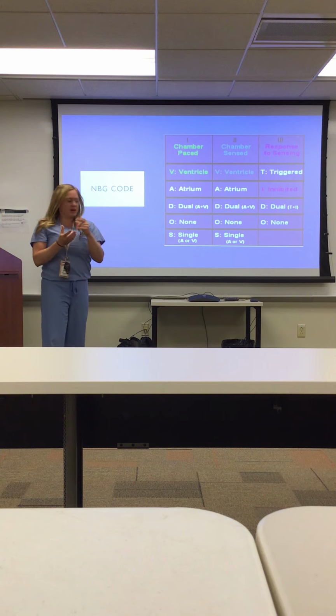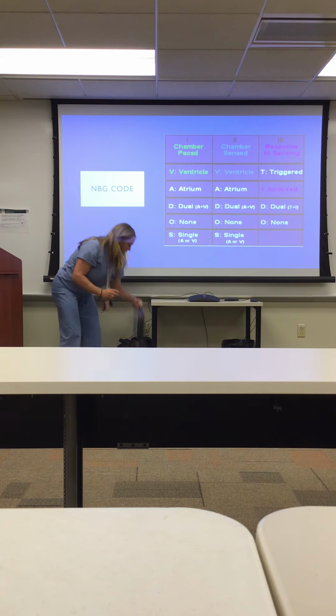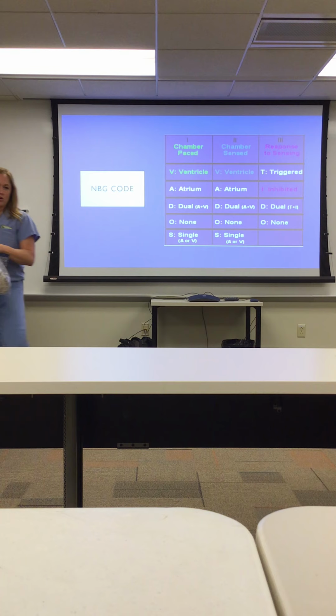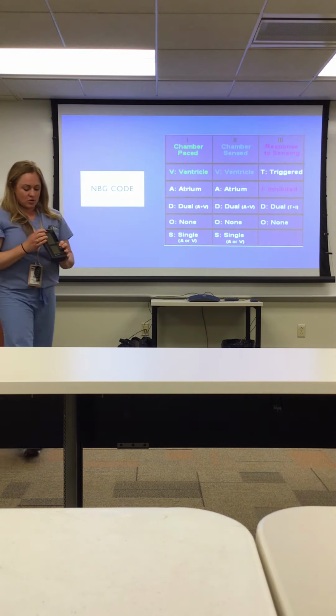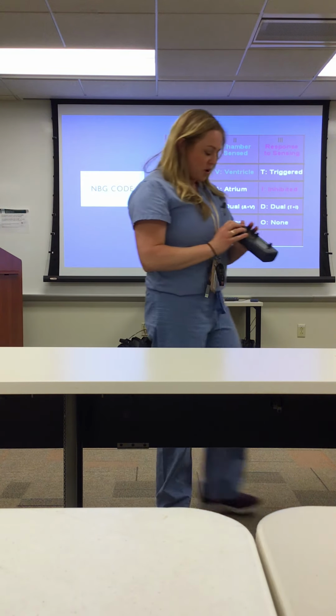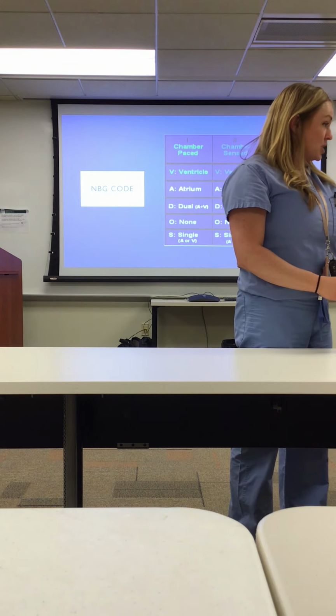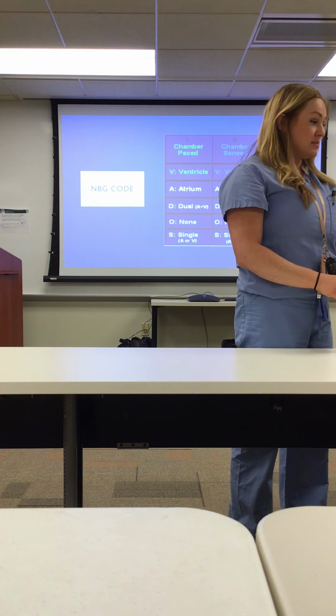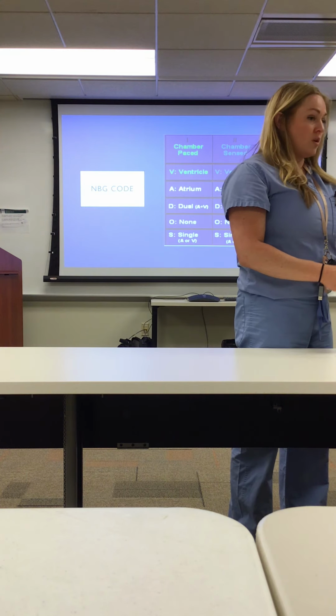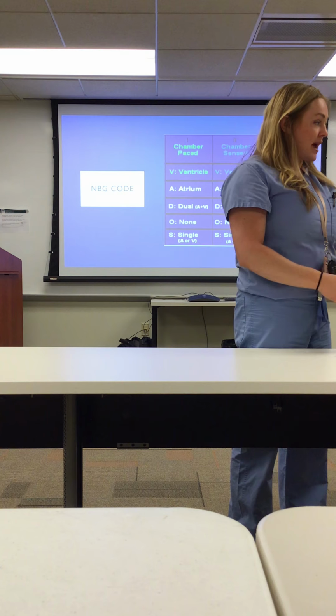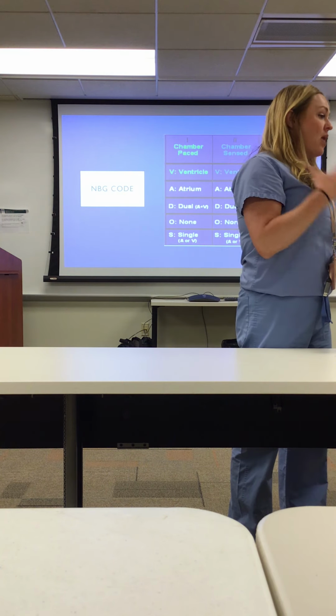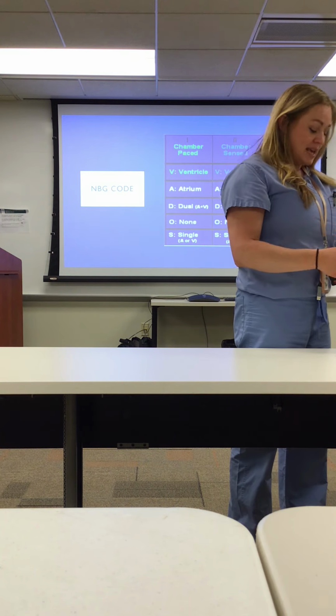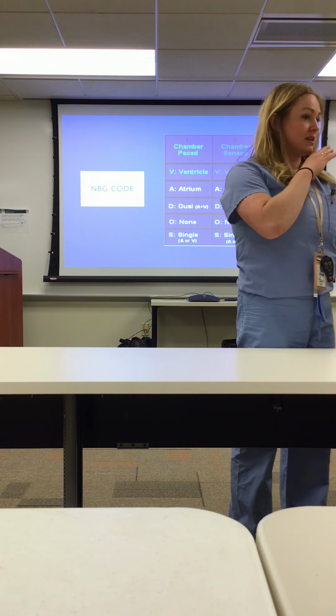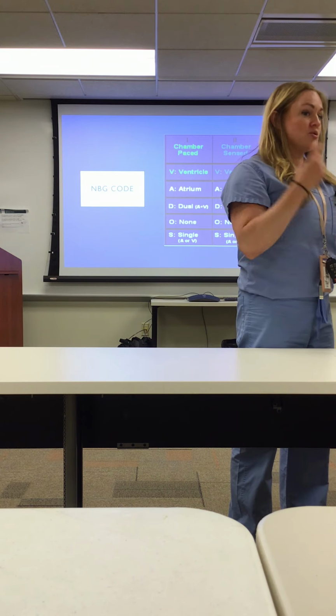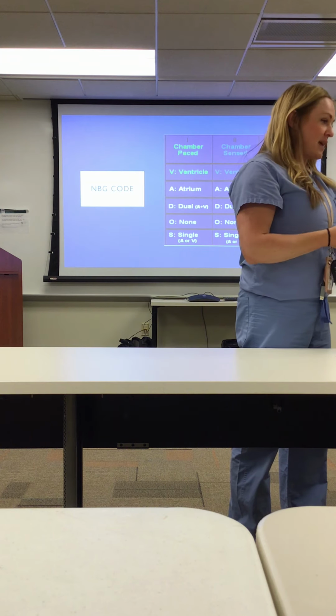And on the temporary pacers, there's actually an emergency DOO setting. I'm not sure if you guys have noticed that before, but it's up here on the right-hand corner. What is that for? This is for if you see a patient that's losing capture and you're not really sure why, and it's pretty serious that they get pacing back. You can always hit this, and it's going to program the device to the max amount of output that will be delivered. So it's going to pace at 80 beats a minute.